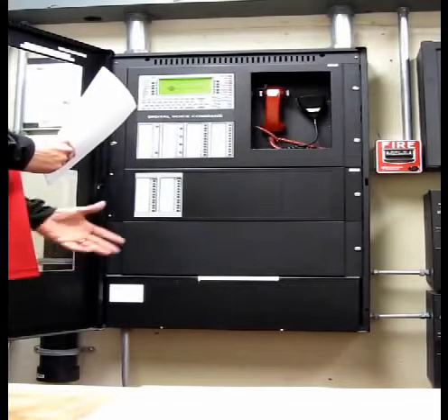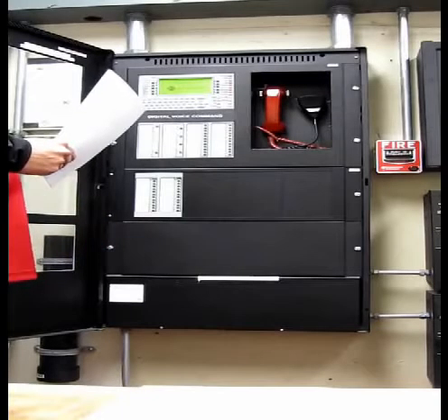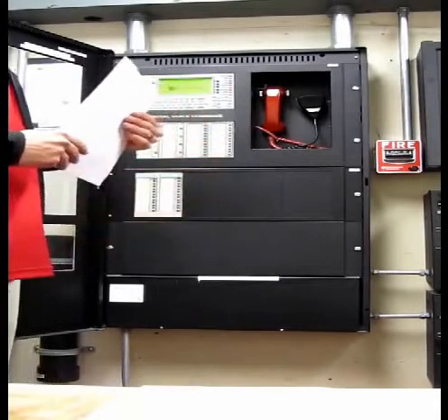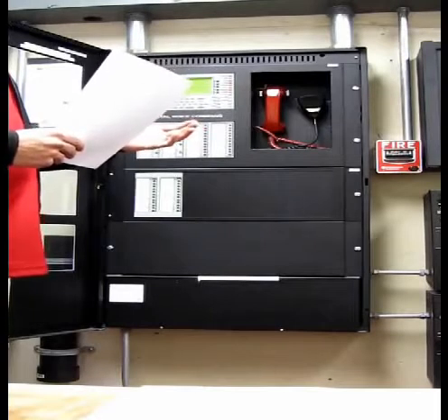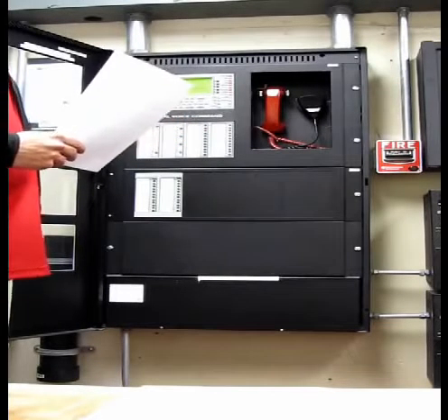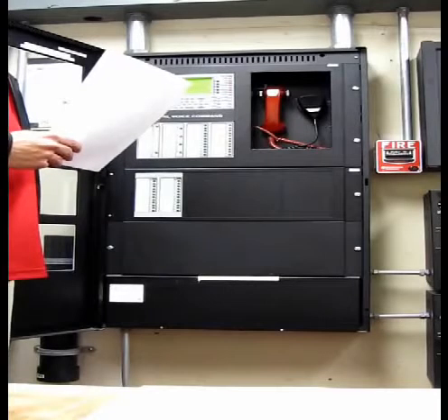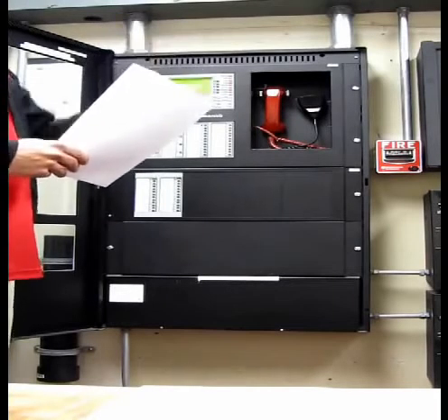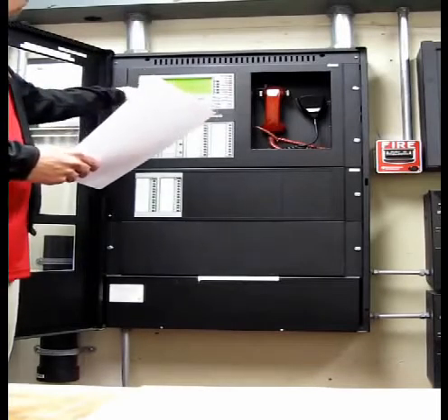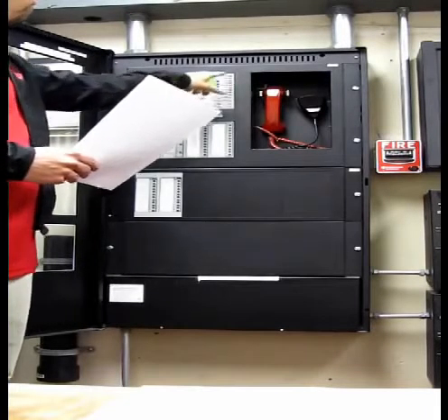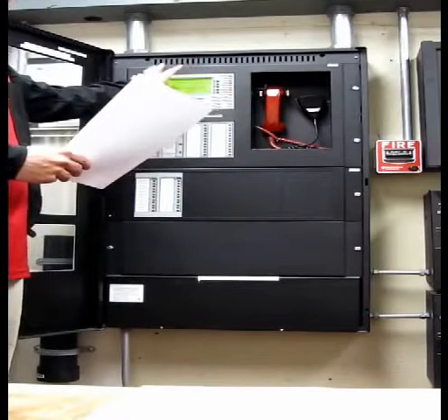Okay, so with that said, let's move on to the supervisory conditions. A supervisory condition is more of like a maintenance alert, something you guys need to check out immediately if it comes in. The only two types of devices that you have here that will cause that is one, a sprinkler tamper valve. If someone closes a valve in one of the stairwells in the sprinkler system, that will cause a supervisory alert. You'll get the supervisory light to come on. Once again, you can acknowledge it, just silencing the local piezo.